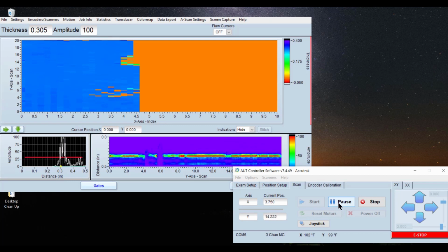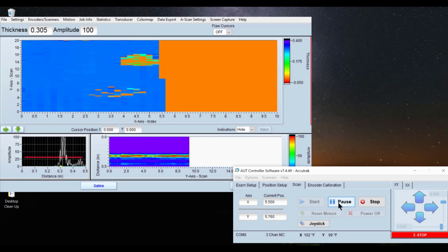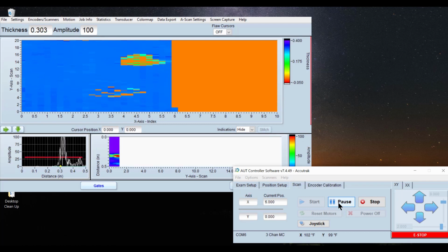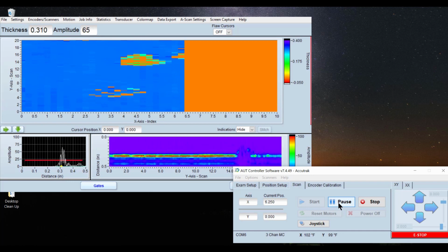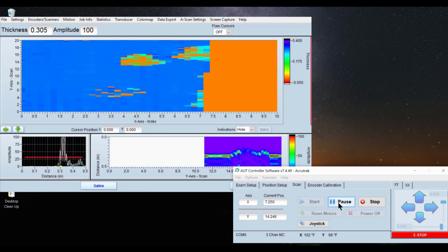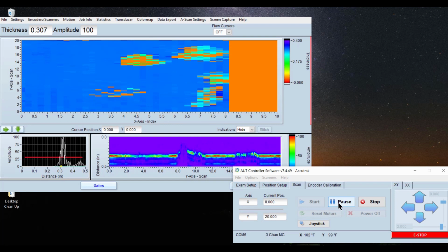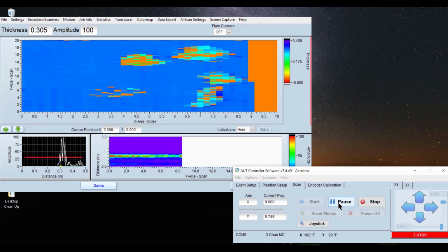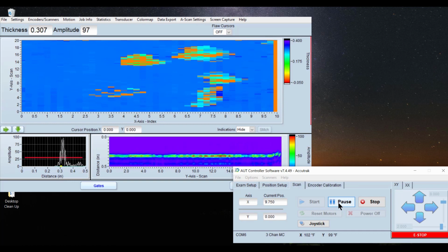So you will notice you'll be able to start to tell whether the scanner is going back and re-recording. You can see some of the indications popping up in your B scan. Looks like we have a nice little bit of corrosion there. Now you'll start to notice that some of these defects look quite pixelated. If you needed to go back and do some in-depth analysis, say you think you might have some possible stepwise cracking or hydrogen blistering, you could simply stop the end of the scan and we'll go through that. Just take a quick second. We'll let this scan complete real quick.